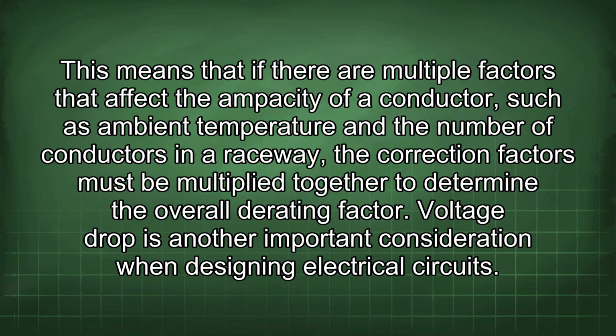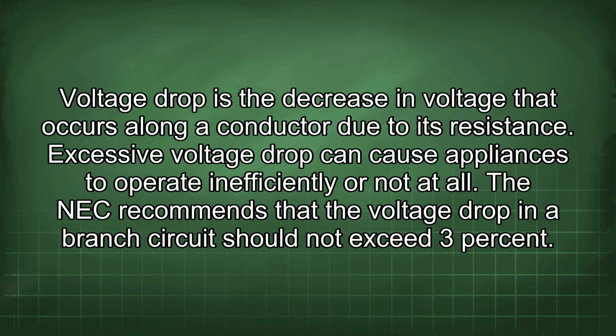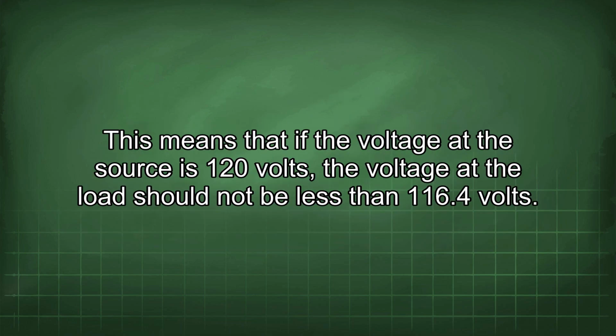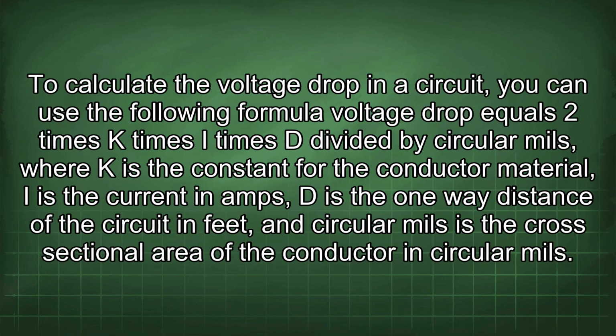Voltage drop is another important consideration when designing electrical circuits. Voltage drop is the decrease in voltage that occurs along a conductor due to its resistance. Excessive voltage drop can cause appliances to operate inefficiently or not at all. The NEC recommends that the voltage drop in a branch circuit should not exceed 3%. This means that if the voltage at the source is 120 volts, the voltage at the load should not be less than 116.4 volts.